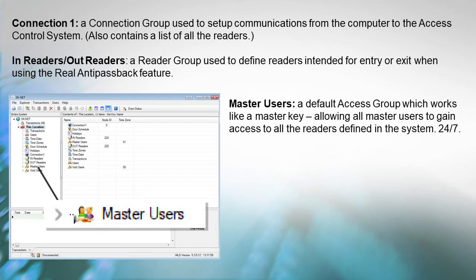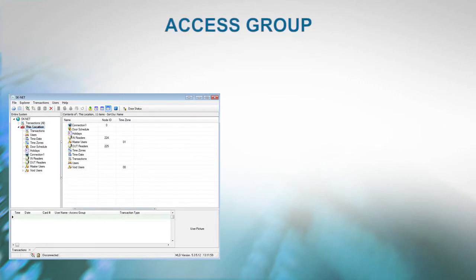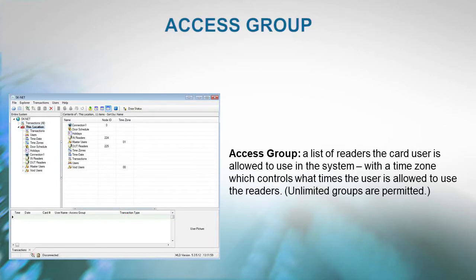Master Users is a default access group which works like a master key. It allows all master users to gain access to all the readers defined in the system 24 hours, 7 days a week. Void Users is also a default access group which denies all void users access to all the readers in the system. This group is used for lost cards or someone who no longer is allowed access. Access Group is defined as the list of readers the card user is allowed to use in the system along with a time zone which controls what times the user is allowed to use the readers.